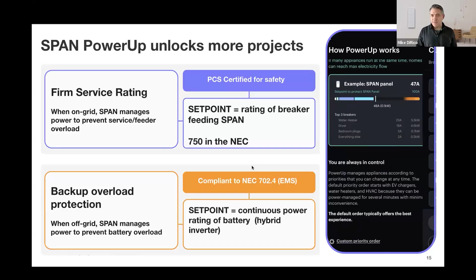So I mentioned backup overload protection - think about your restricted loads, air conditioners, those kinds of things on a single battery. You've probably been through this before, where a battery was maybe not appropriately connected by some other installer - not you, somebody else did it incorrectly - and you ended up with a brownout or blackout on that battery and had to do a truck roll. This is what we talk about: the screen you're seeing flash here is what homeowners are going to see, giving them a warning that you don't want to add these devices into your battery priority because it could potentially overload that battery. Just be aware of that.